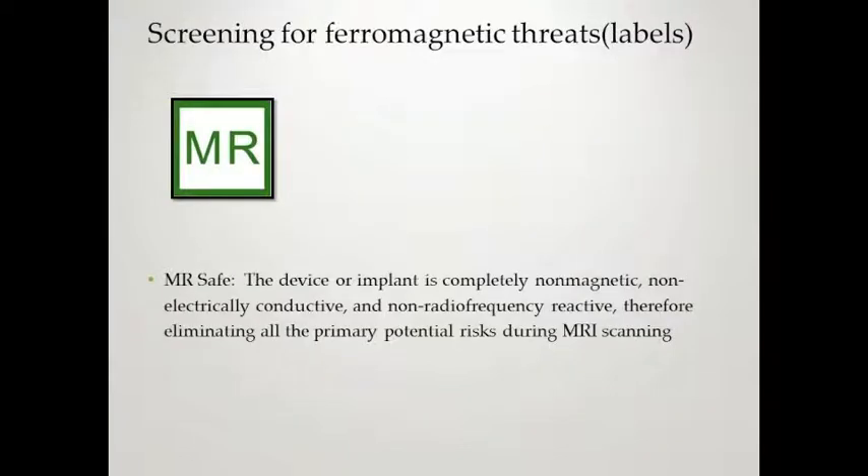We're going to look at labels. The MR Safe label means the device or implant is completely non-magnetic, non-electrically conductive, and non-radiofrequency reactive — eliminating all potential risks during MRI scanning. You cannot go by color alone. Green is not an indicator of MRI safe on other items. Oxygen, for DOT labeling, is a green label — that doesn't mean it's MRI safe. The MR Conditional label means the device or implant may contain magnetic, electrically conductive, or radiofrequency reactive components that are safe for operation in proximity to the MR, provided certain conditions are met.